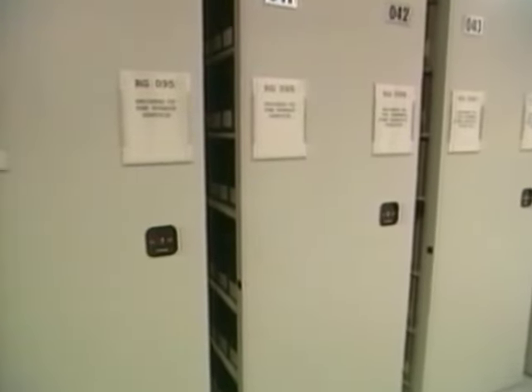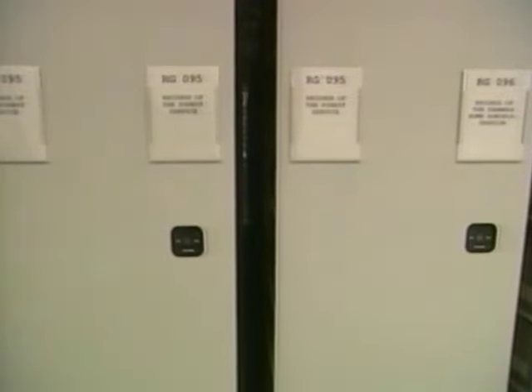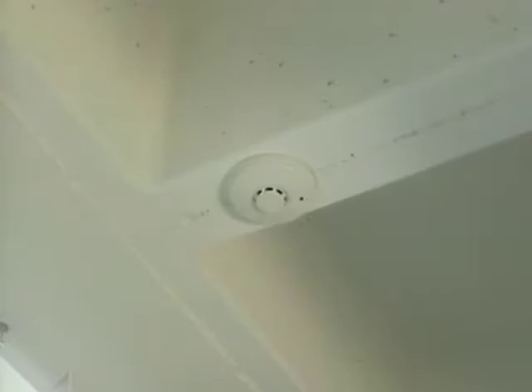The fire safety system in the record storage areas is a wet pipe sprinkler system. We accomplish this through, one, a rapid response sprinkler head that goes off at a lower temperature. We also are able to, using the electric system, create what we call a flue space. And that's a space of at least 4 inches between each of the carriages that allows the smoke to get to the smoke detectors and the water from the sprinklers to get to any fire that might break. The third thing that we did was put in smoke detectors in all the record storage areas.